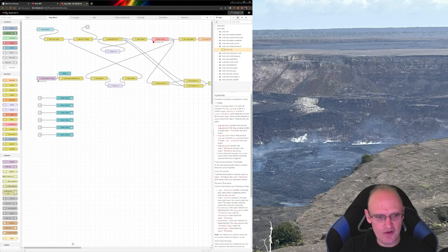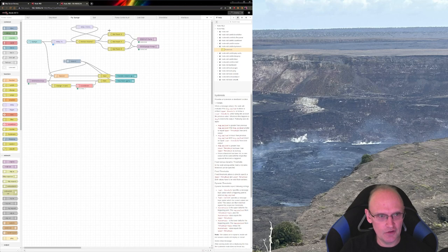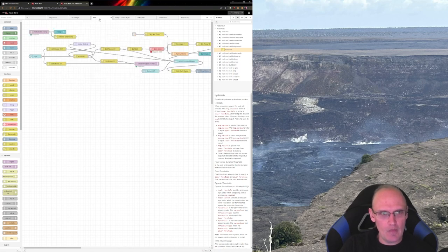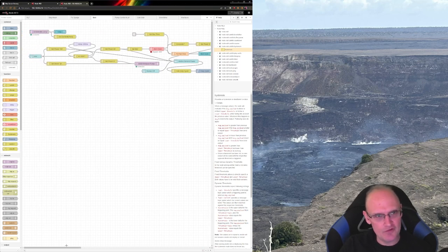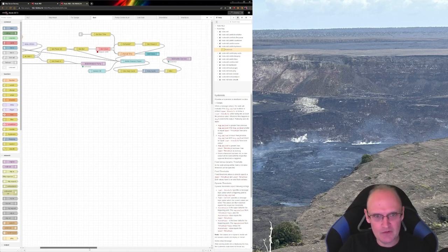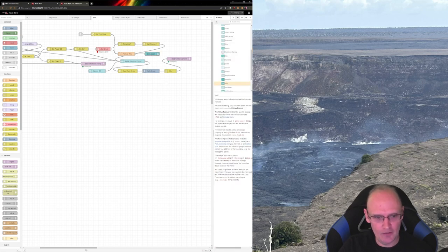We've got step mash logic over here. I've got logic for my fly sparge. This controls two different pumps to get them equalized and flowing at the same rate. We've got logic for the boil, which turns on the whirlpool pump at the beginning, turns it off when it hits temp, and turns it back on at the end of the boil. There's a boil clock in here that counts down.